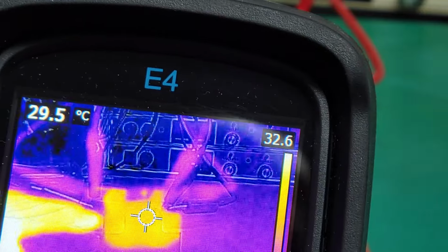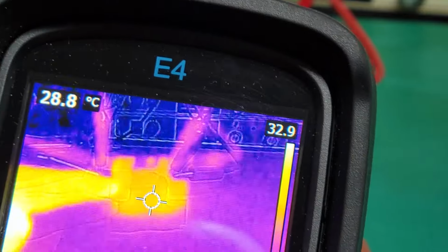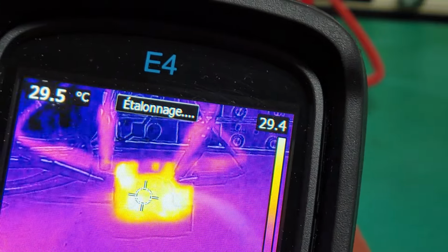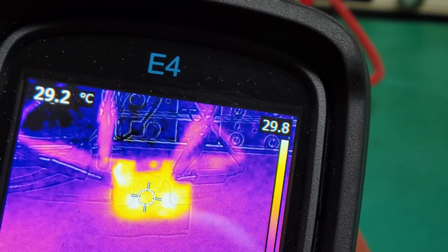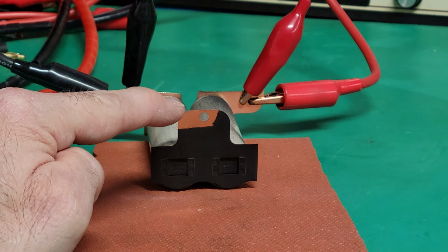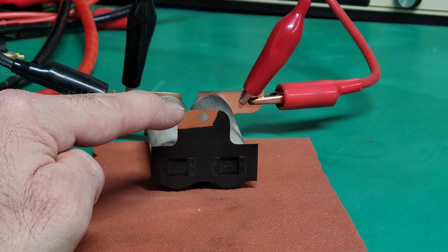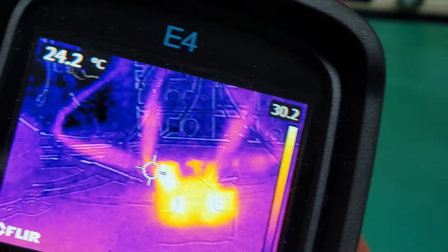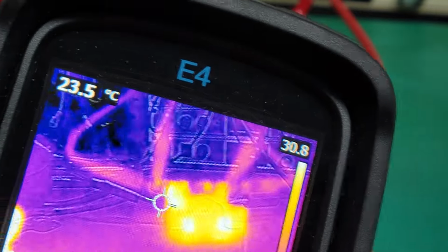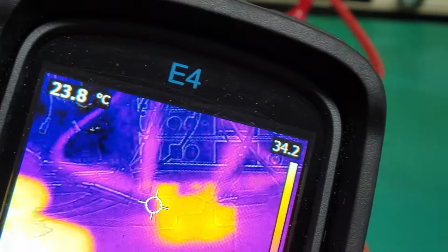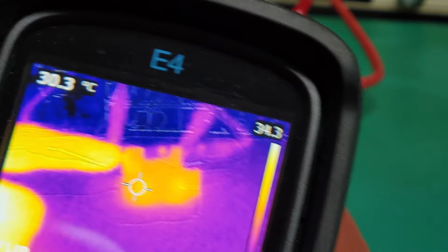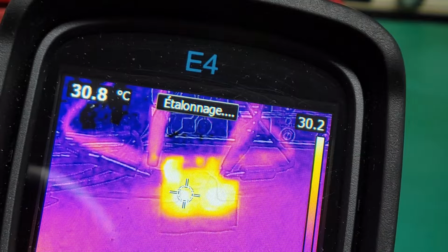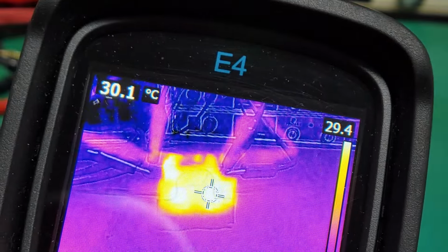It's interesting to see how the black paint is actually affecting. You see just a little bit here above here. This is the area where there's no paint. So this area makes you believe that it's colder, but it is not. It's just that the way that this surface is transmitting the heat through this bolometer sensor here, it's different and it needs to be corrected. So I'm using black paint in order to do that. So you see it's about 30 degrees for this one and 30 degrees for this one too.